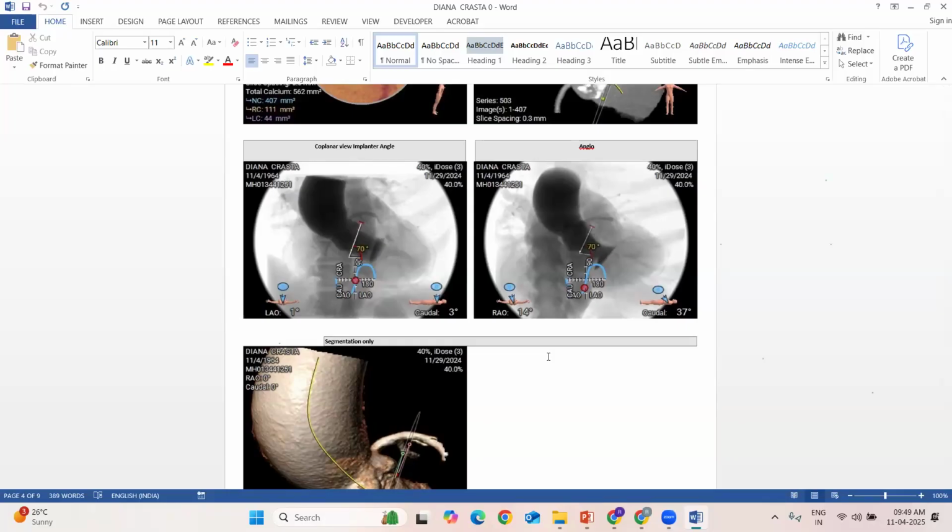Right. Dr. Rajan, one doubt. In simple one sentence, the implant will be happening on RAO view, and before the implant, it is confirmed through an LAO caudal, right? Yes, yes. Always they will implant on RAO only, right? Yeah, because otherwise you will not get the proper depth of the device.